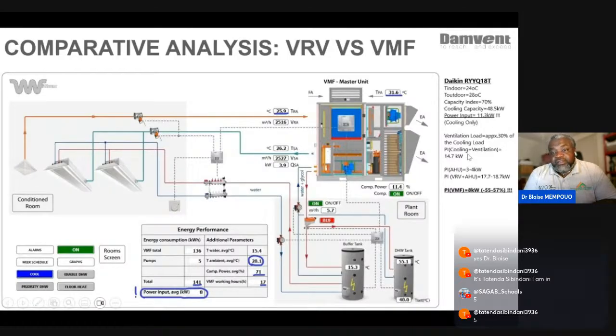kilowatts. And as you know, if you have a poor ventilation system, you also add approximately 30% to your cooling load using the conventional system. So that makes a total cooling load of 40.7 kilowatts, compared to our one, where we are around 8. The total power input here is 14.7 kilowatts, whereas our average power input is around 8.